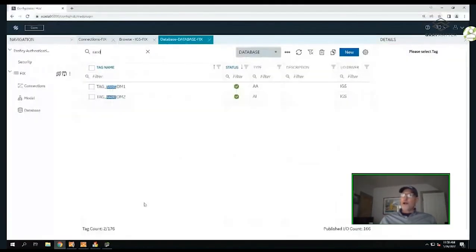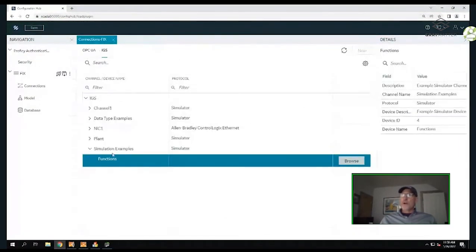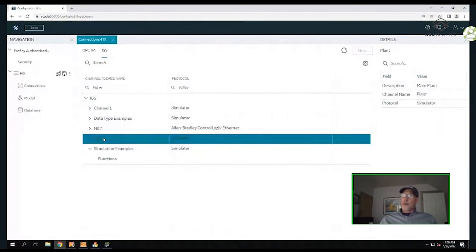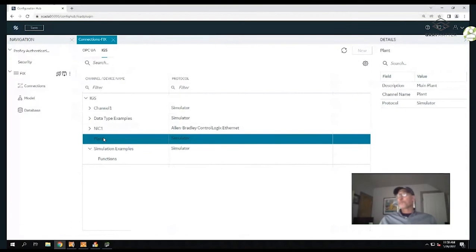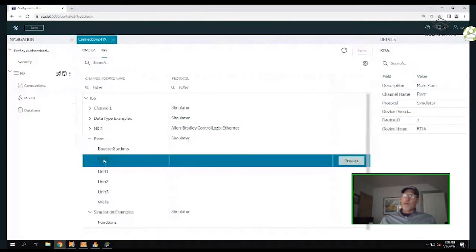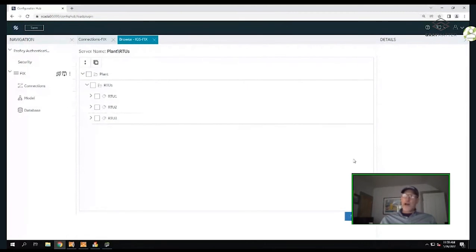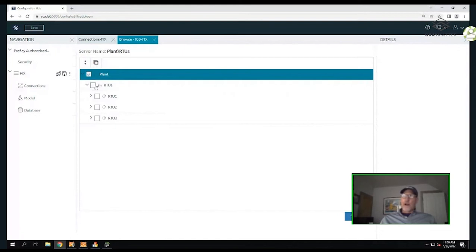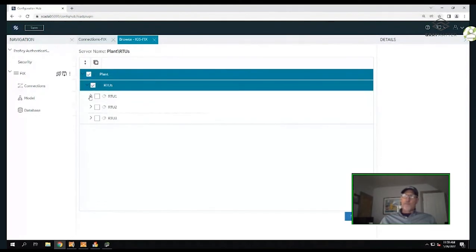Moving on, I'm going back to Connections, and this time I'm going to build a model using the same structure from the Industrial Gateway Server. I'll drill down into my plant - in my plant I have RTUs - and I'm going to browse into the RTU, which drills into that group of tags or device and shows it in the Configuration Hub environment. I can now select to create a hierarchy using that same hierarchy I've already built in the controller, and use that in iFIX.